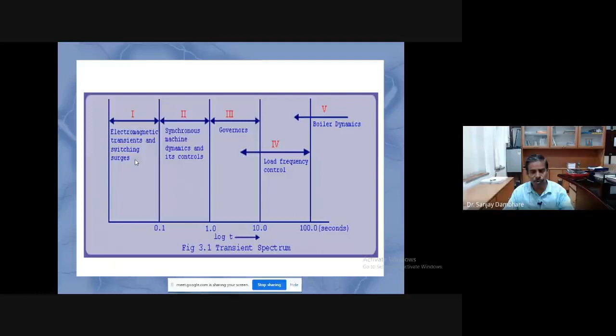We know that to maintain the transient stability of a system, which is equally important, which may be hampered because of the fault, the speed of the relaying is important, right? So let's take this situation that the generator is supplying power to the system over two transmission lines, and there is a fault on one of the transmission lines, right? So in this situation, what you should do is isolate this transmission line as quickly as possible, and possibly you can then transmit some power over the healthy transmission line.